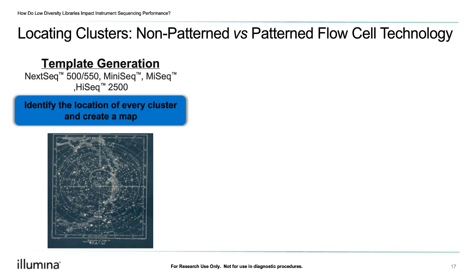Before we dive deeper into each metric, let's briefly discuss the difference between pattern and non-pattern flow cells. For non-pattern flow cells, such as those used on the NextSeq 500 and 550, MiniSeq, MiSeq, and the HiSeq 2500 instruments, clusters will be randomly distributed across the flow cell surface. Because clusters are generated randomly, the instrument does not know where they will be located, and will use the first few cycles to map the location of the clusters. This process is called template generation, which is similar to mapping stars using an algorithm like those used to generate star charts in astronomy.